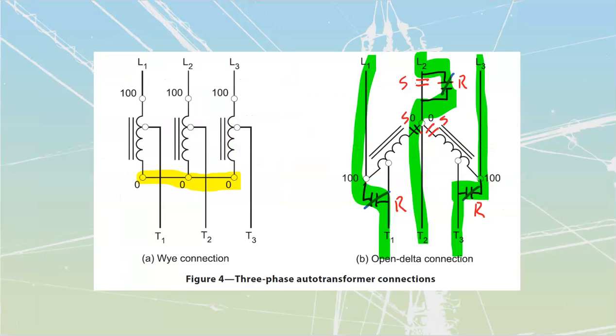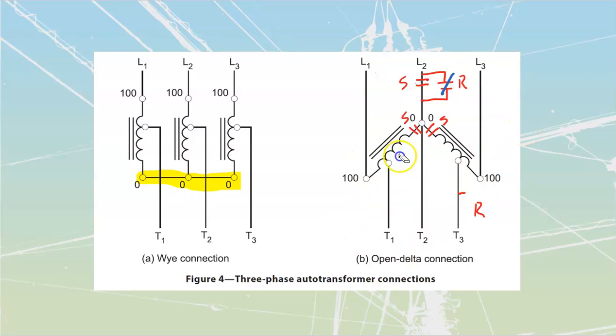I mean, really, when you take a look at both of these, either the Y type of connection or the delta type of connection that we had off of these, both of them are highly useful for reducing the value of voltage that I'm going to have out to my motor when I utilize them, as well as reducing the total amount of current that I'm going to have in.